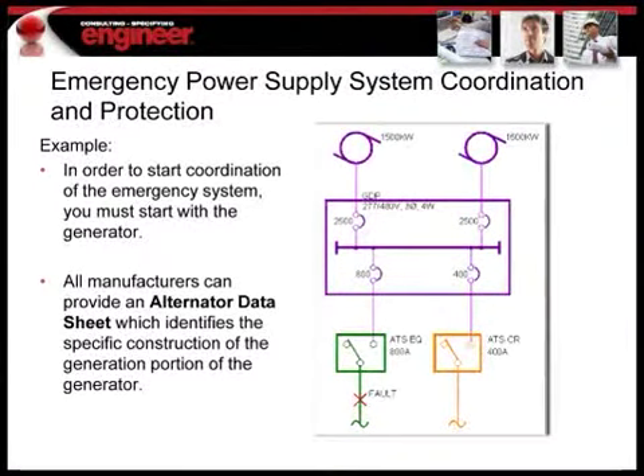So when you're doing a coordination on an emergency system, you have to start with the generator. The first thing you need to do is to get the parameters for the generator, model the generator, and then start your coordination. If you start down at the lowest level, at your 120, it may all be changed by the time you put in that generator. It may change everything. So the first thing you need to do is model your generator, and then work your way down the system.